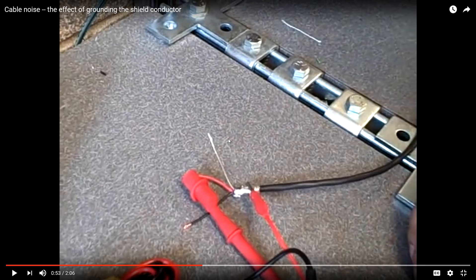I'm reinstating it: you must, there is no way around it, you must terminate the drain wire. Just solder on either a circle clip, or you can extend it with a wire. A lot of people will say it's not that long. You can solder on another lead of 20 gauge and just terminate it with a circle clip. I love the circle clips because you can screw them in to wherever you're trying to attach it to your earth ground, and you're set to go.